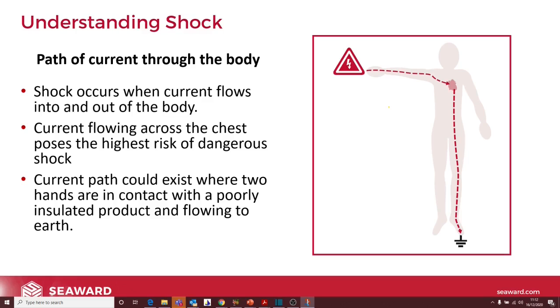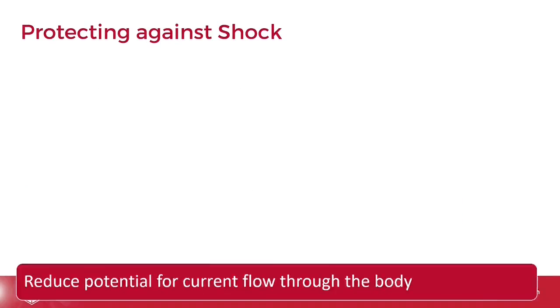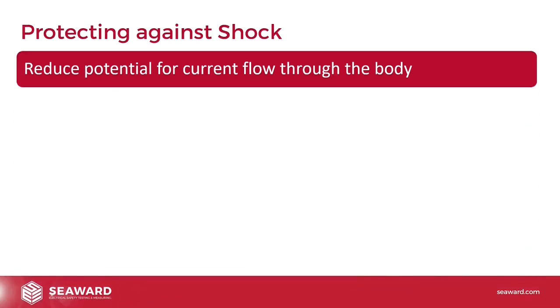Current flowing across the chest poses the highest risk because that's where your heart is. And the current path could exist where two hands are in contact with poorly insulated product and flowing to earth. So that could be that your left hand is touching the equipment that you're testing and your right hand is touching something else that's grounded. So it might not be that it has to go through your feet, that your feet are grounded. It could be that it goes into you one arm and out of the other arm, and that would cause a shock.